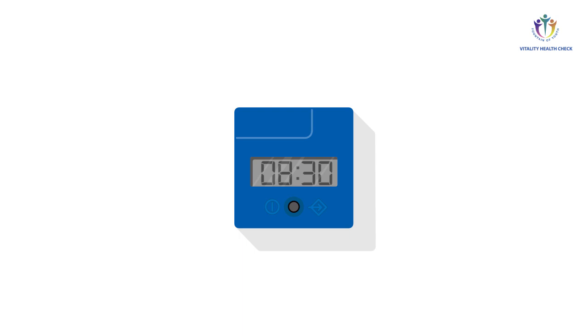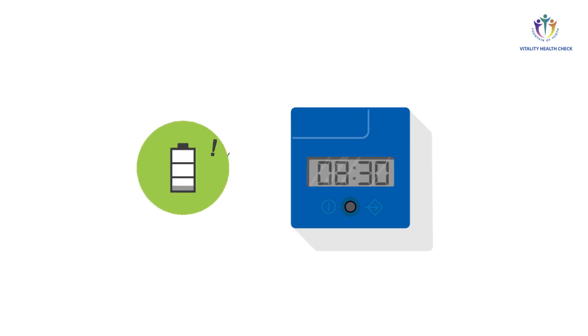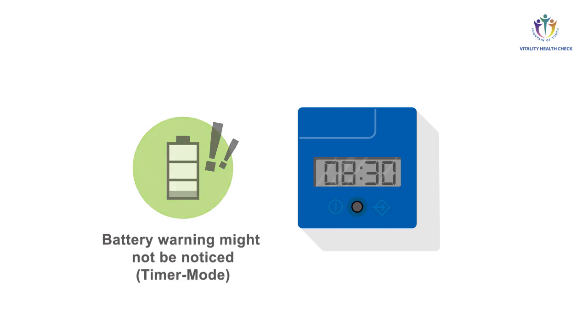If you frequently run the VHC reader in timer mode, it might happen that you don't notice the battery warning symbol is showing up during countdown, because you come back only after the countdown is finished to read the quantification results. Thus, in case you frequently use the timer mode, it is recommended to ensure permanent power supply via the data reader cable.